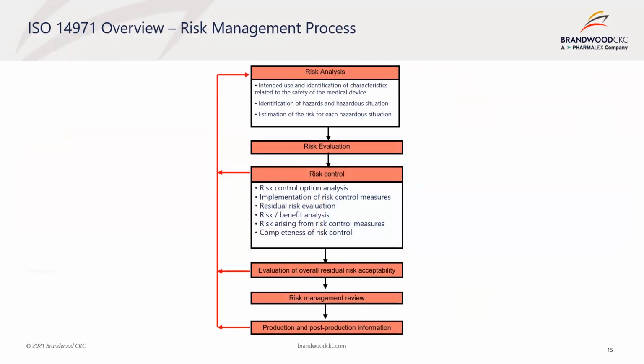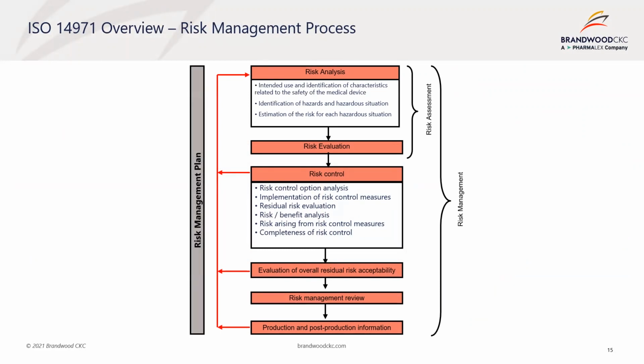This diagram describes the typical workflow of the ISO 14971 risk management activities, which we'll briefly look at each one. I should highlight that it is important to understand the terminologies here, specifically the difference between risk assessment, which includes risk analysis and risk evaluation, and risk management, which covers the whole process. Also, the risk management plan is shown, which is a document that defines the whole process for a particular device. Keep in mind that the risk management process is an iterative one. That is, experience of the device used in the field will allow manufacturers to learn, iterate changes, and develop further knowledge of the risks.